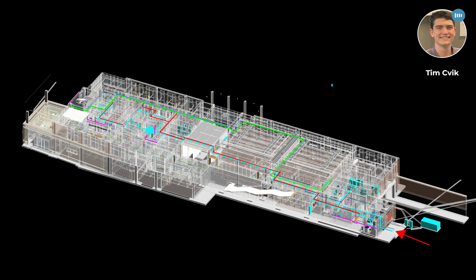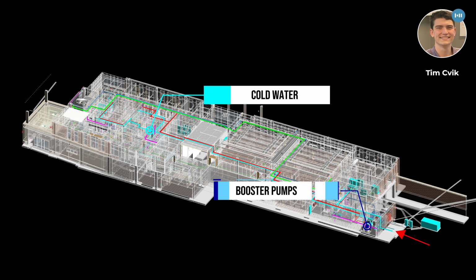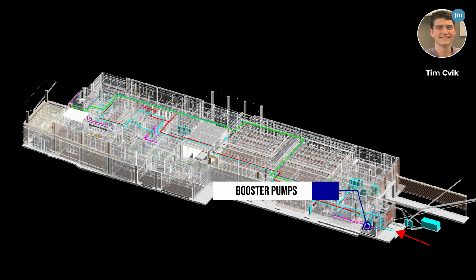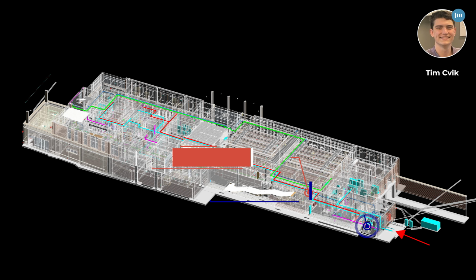Cold water, shown in cyan, enters the building into booster pumps located in the mechanical room. It is then distributed to sinks, showers, toilets, and other fixtures as required through piping running in the ceiling. Hot water, shown in red, is heated in the mechanical room by water heaters to 140 degrees Fahrenheit to prevent growth of bacteria.